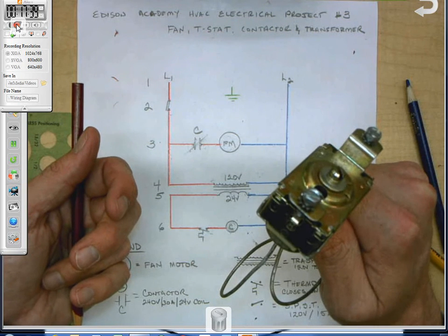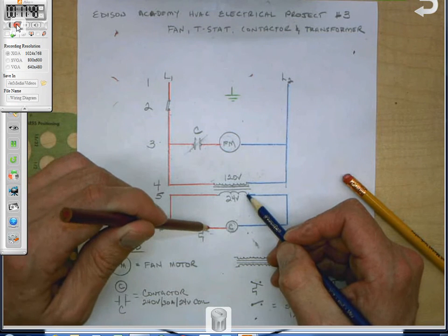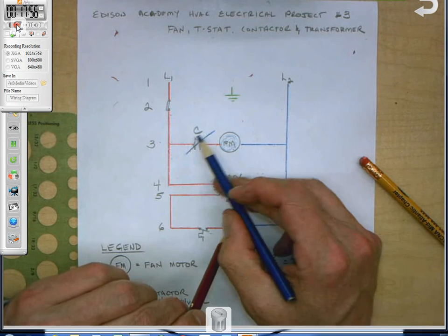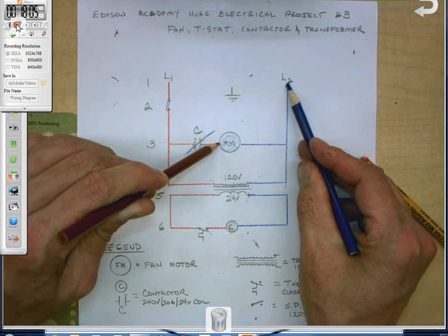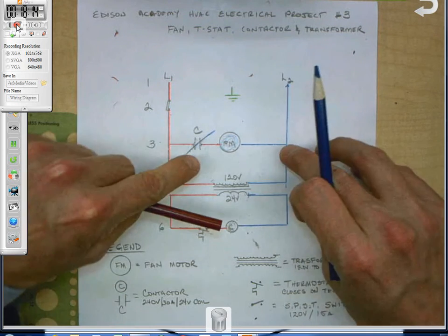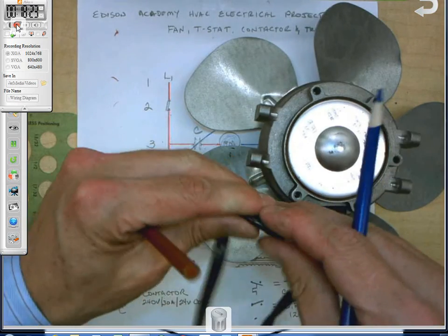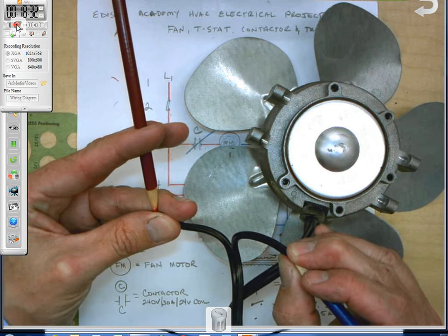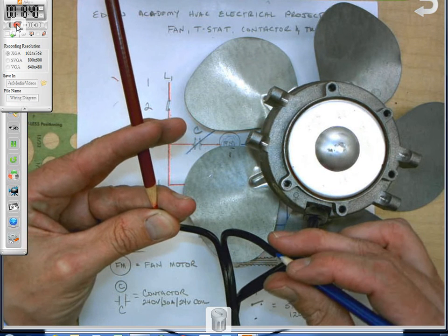But if I'm holding it, and I've got it set down to the coldest setting, and it still doesn't energize between this to this, I've got a bad thermostat. So I've got to change out my thermostat. Put a new thermostat in, if I'm reading 120 volts here, 120 volts here, or 24, I'm sorry, 24 volts here, 24 volts here, and 24 volts there. Then this should energize, which means my fan motor can come on. Now, if this is energized, and I'm reading 120 volts here and here, but the fan motor isn't coming on, what's my problem? I got the voltage, but the motor isn't spinning, so what does that mean? Bad motor, bad fan motor. So I would disconnect the power, pull these leads off the motor here, and this is where I'd switch gears. I would start, instead of measuring voltage, I'd pull the leads off and measure resistance. Switch the meter to resistance, and if I'm reading some resistance, the motor's probably good. If it reads zero, well, it's not good. It's got to have some resistance, and the value's not important. Each motor has a different value of resistance, but if I read some resistance, that means it's probably good. And then if I read nothing, where it says OL, open link on my meter, well, that means the winding burned up, and it's open inside somewhere, and it's not making contact. So yes, you'd have to change out the fan motor, put a new fan motor in, and we're done.